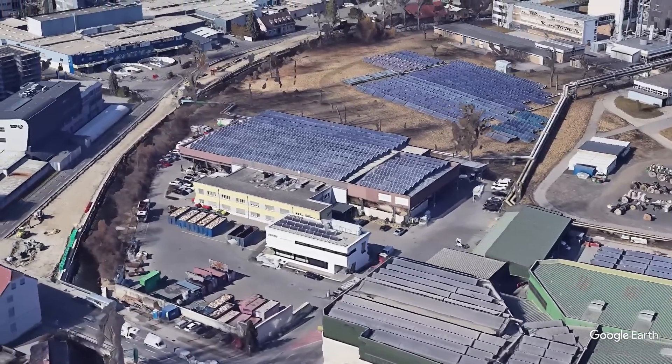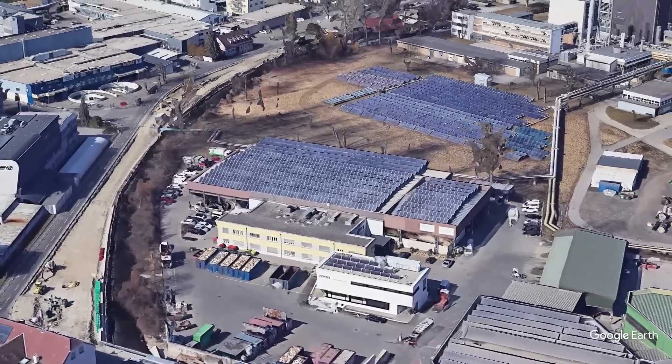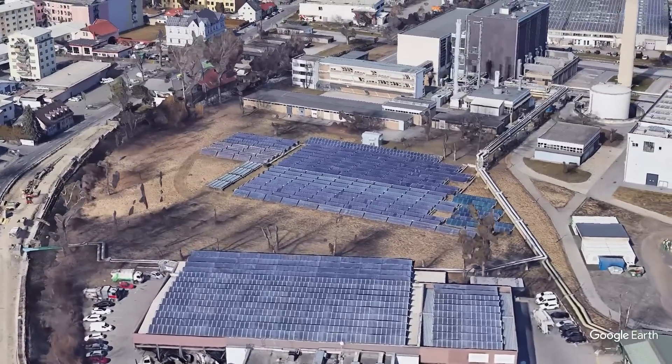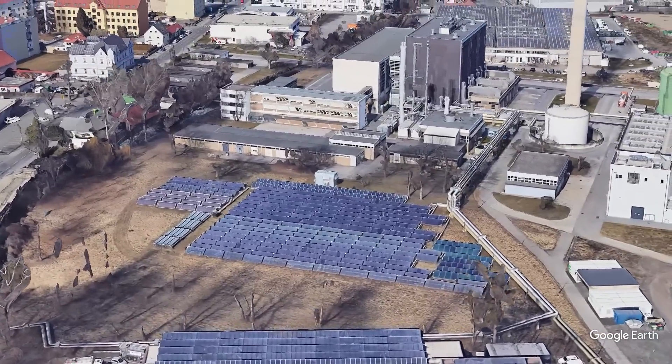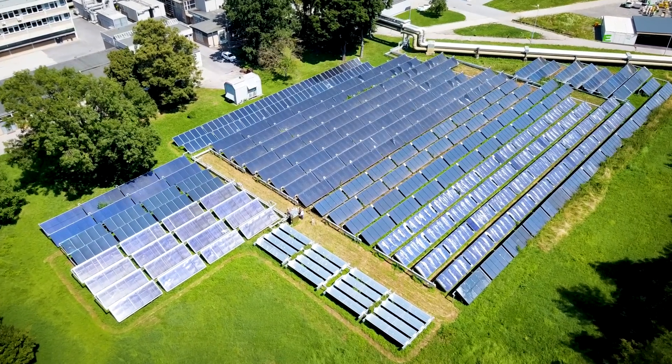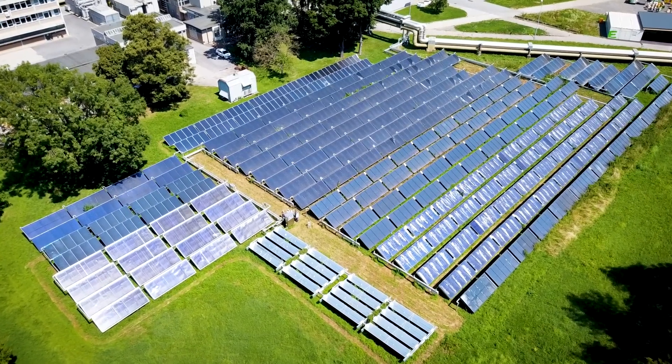There's only 100 square meters of a specific brand of collector that has been discontinued. The entire capacity is still functional and is still being serviced and maintained by SOLID. We've had in excess of 15 years of clean, beautiful solar thermal heating going into the district heating loop. The district heating system of Graz requires a peak load of 550 megawatts of thermal energy.